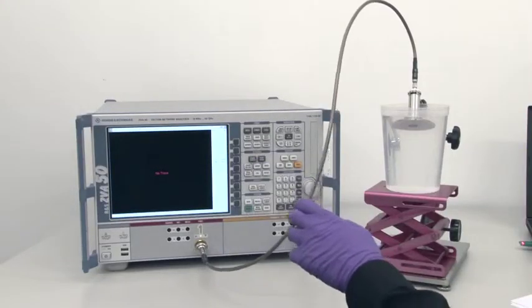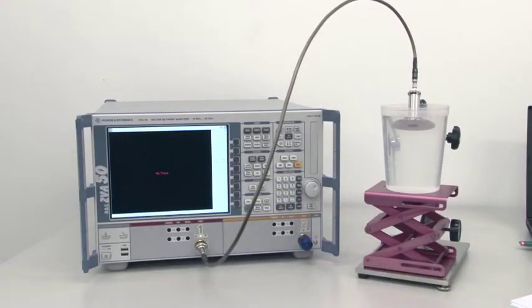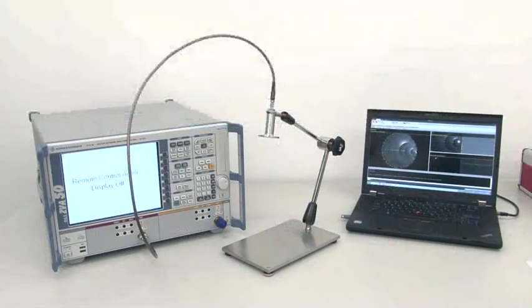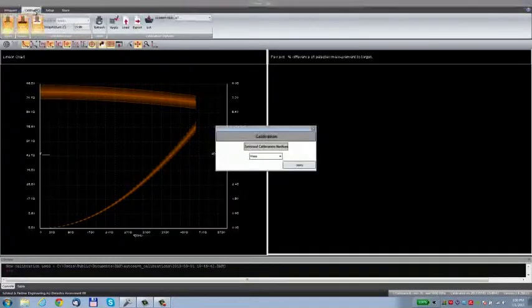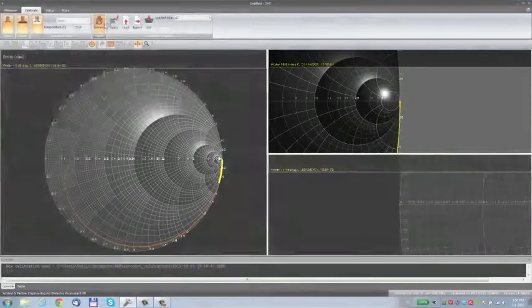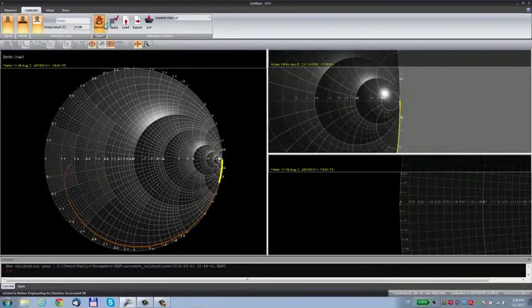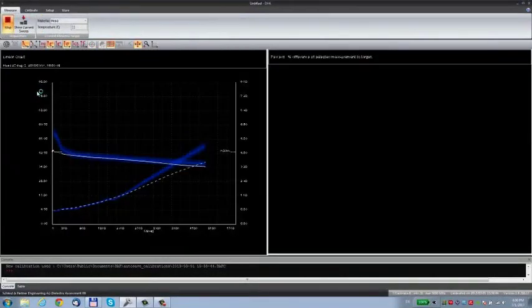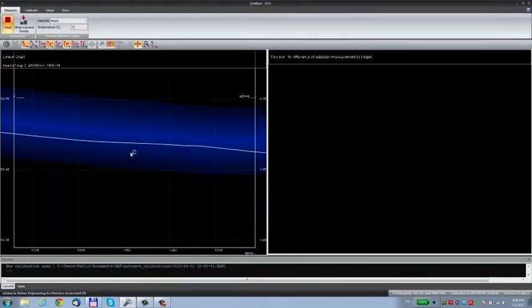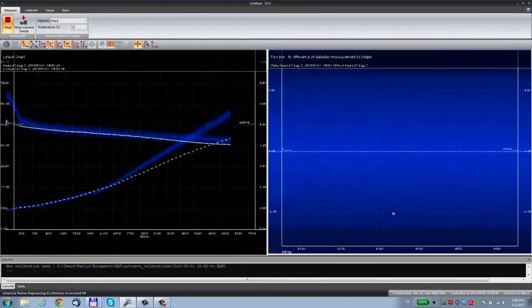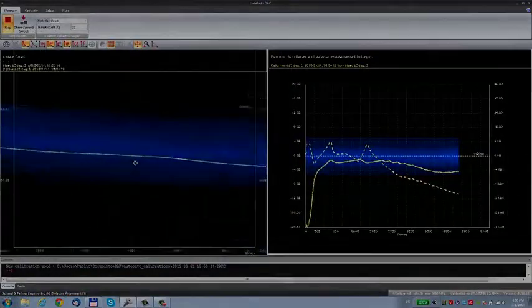When you touch the cable by accident, you don't necessarily have to repeat the calibration. Leave the clean probe in the air. Go to the Calibration tab and click on Refresh Open. It will only replace the open calibration standard in the last calibration and recalculate the correction coefficients. Apply the new calibration. If you see any irregularity in the measurement, like wave on the curve, then the refresh was not sufficient. You should repeat the calibration.